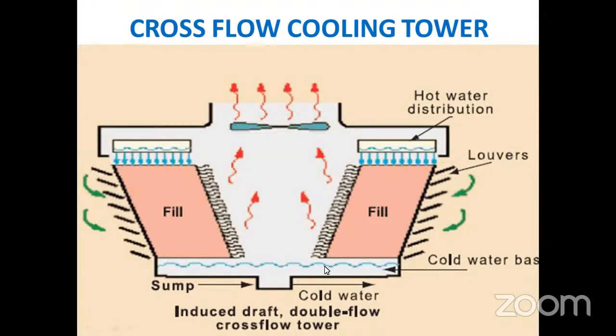Sir, this is called the cold water basin, sir. The bottommost point is the cold water basin, and the slight depression you can see is the sump. These are louvers. These are called fill. This is the fan. Theoretically speaking, the upward red arrow should be hot air only, but it is not happening. Hot air with water vapor goes out to the atmosphere, making a water loss.